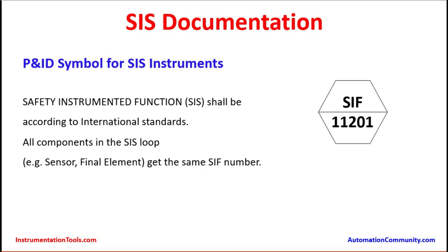As part of this documentation, safety instrumented functions also need to be earmarked exclusively in the Piping and Instrumentation Diagram (P&ID). Safety instrumented functions shall be represented according to international standards — sensors and final elements involved in the SIS loop will be identified with a hexagonal symbol. The SIF number is a sectional symbol indicating the component is used in a safety instrumented system function, and it will carry a number. All components in the loop — the sensor and the final element — get the same SIS number, which corresponds to a particular hazardous condition and scenario.